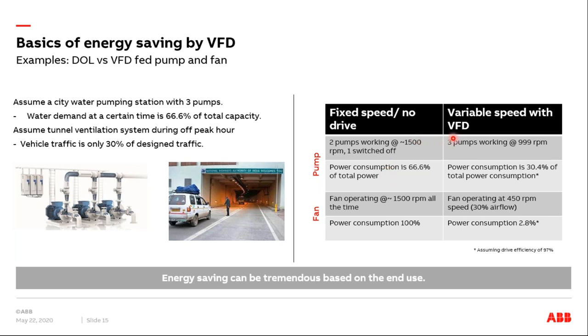If you change to a variable speed system with a VFD, there are three pumps working. By the way, I have used three VFDs here, but it could be one VFD that is used to operate all three motors. So now, with three pumps working, we can operate these pumps at around 1000 RPM, and it should be able to provide the 66% required water demand. But because you are changing the speed of these pumps, even though you are working with three pumps, you reduce the power consumption to 30%. So you have nearly 35-36% energy saving just at that instance.